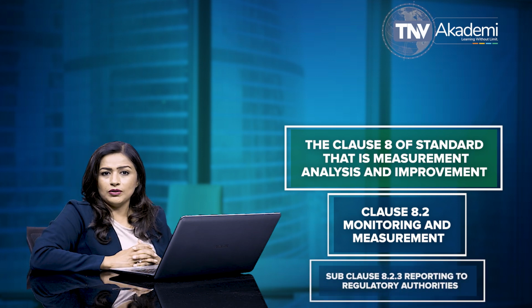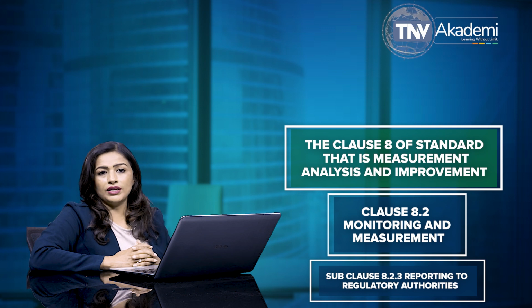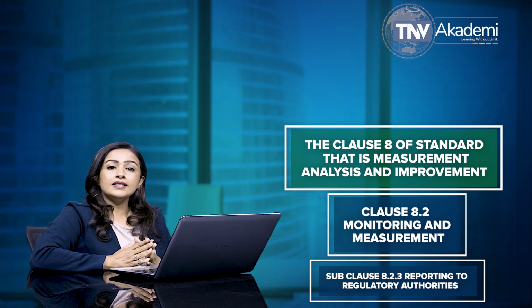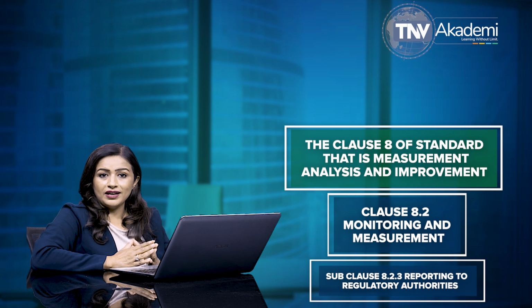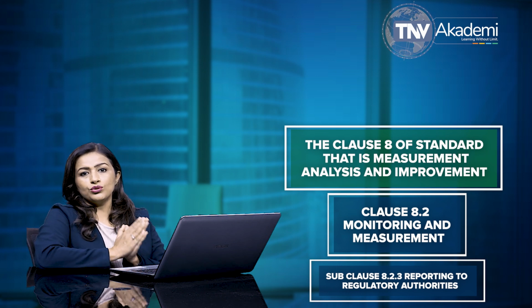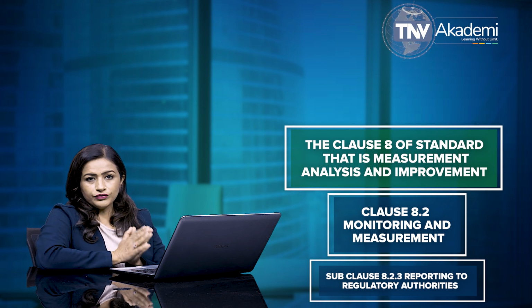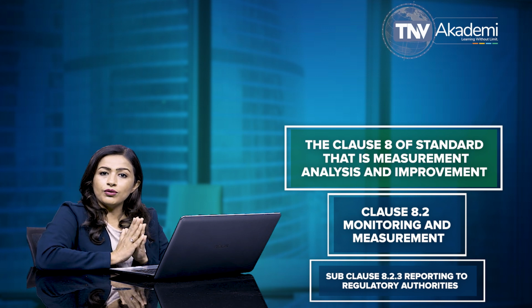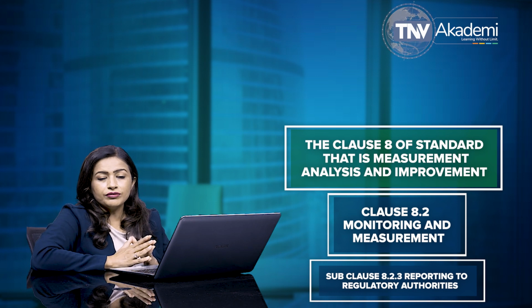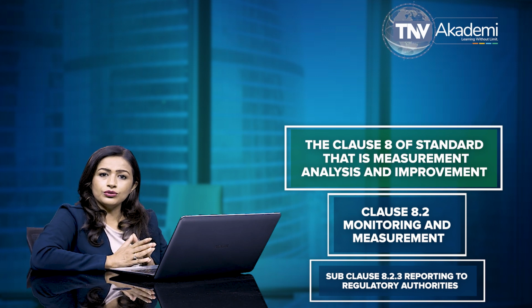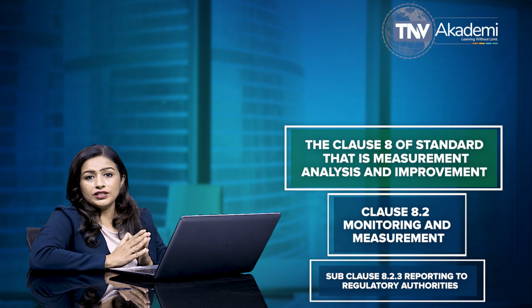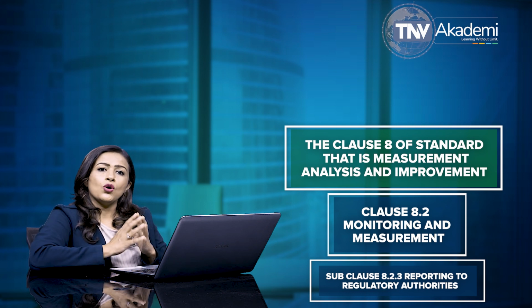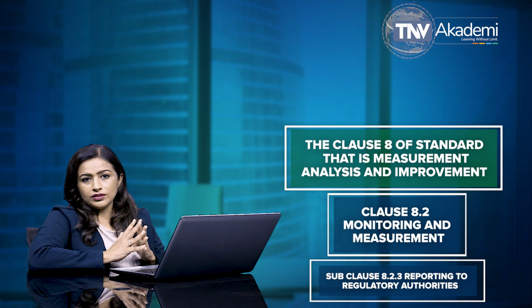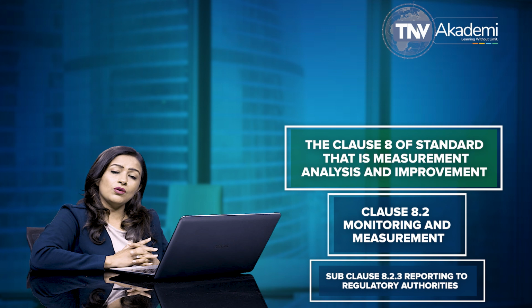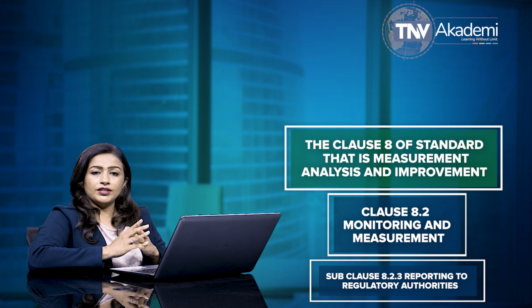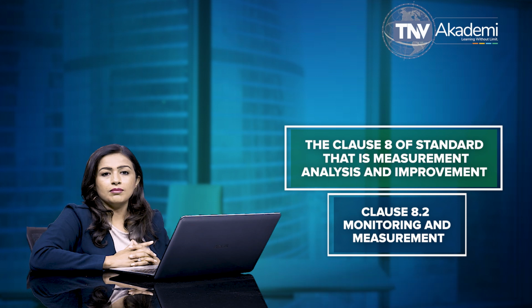Let me discuss now the subclause 8.2.3, reporting to regulatory authorities. This subclause 8.2.3 specifies that the organization is required to document procedures for providing notification to the appropriate regulatory authorities, if applicable regulatory requirements require notification of complaints that meet specified reporting criteria of adverse events or issuance of advisory notices. Further, according to this clause, records of reporting to regulatory authorities are required to be maintained by the organization.